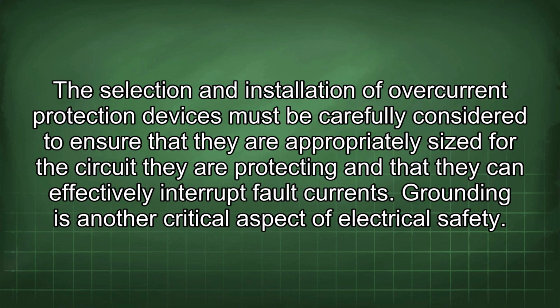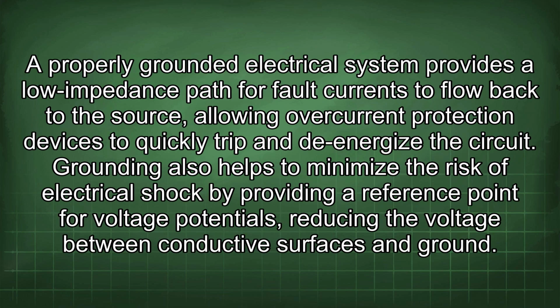Grounding is another critical aspect of electrical safety. A properly grounded electrical system provides a low impedance path for fault currents to flow back to the source, allowing overcurrent protection devices to quickly trip and de-energize the circuit. Grounding also helps to minimize the risk of electrical shock by providing a reference point for voltage potentials, reducing the voltage between conductive surfaces and ground.